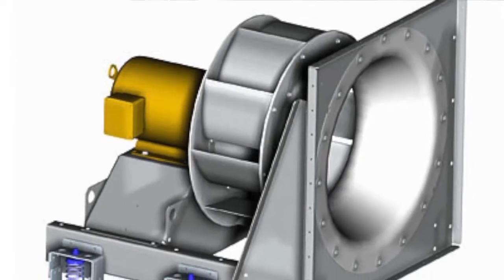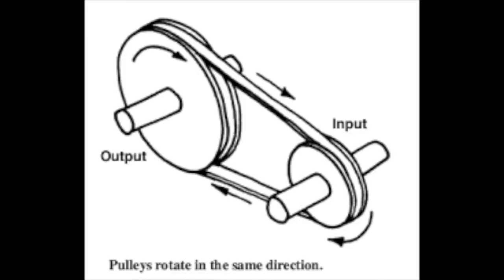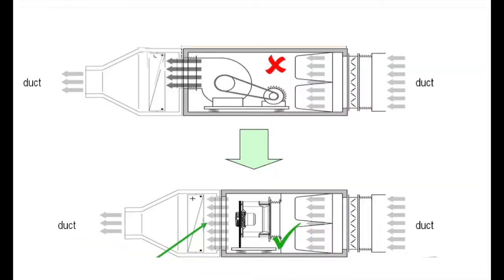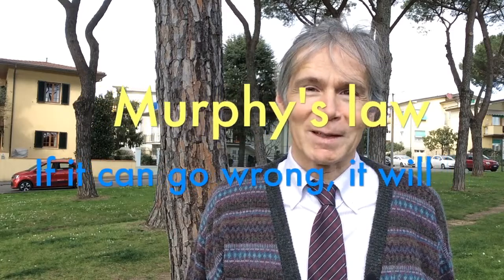Also for compliance reasons, maybe. During my career with Siemens, I still saw many ventilation systems with fans driven by belts. They have many disadvantages. They consume about 33% more energy for the same air flow. They cost more to install — the wheels for the belts must be exactly in one plane and the belt must be held at the right tension. The belts are noisy and are also a bit dangerous for your hands. They need more space. They need maintenance, and this causes the worry that they can fail at the wrong moment — which is mostly always.